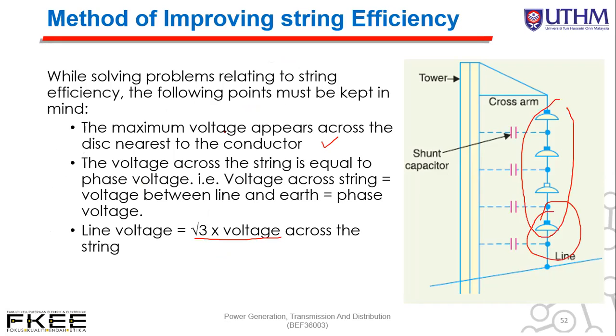Alright. While solving problems relating to string efficiency, the following points must be kept in mind. First, the maximum voltage appears across the disc nearest to the conductor. Okay, we explained earlier, the maximum voltage appears here, nearest to the conductor. The voltage across the string is equal to phase voltage. Here is the phase voltage. Line voltage is root three times the voltage across the string.